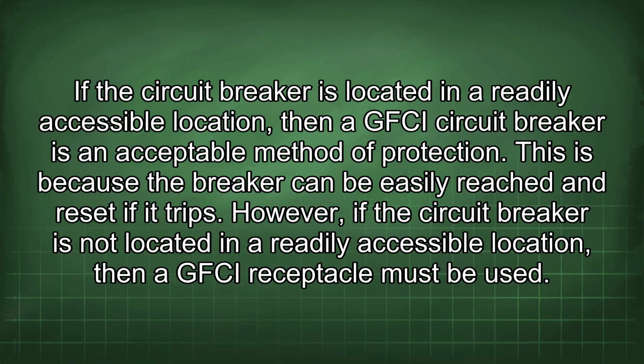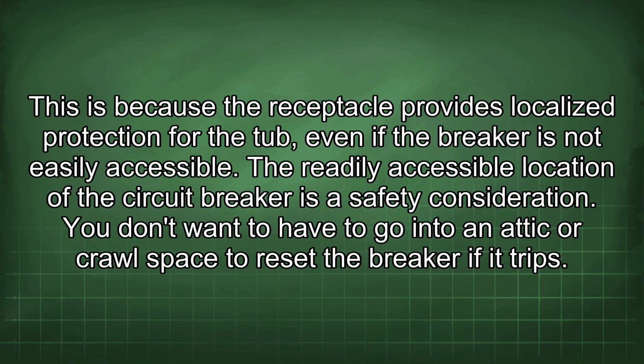However, if the circuit breaker is not located in a readily accessible location, then a GFCI receptacle must be used. This is because the receptacle provides localized protection for the tub, even if the breaker is not easily accessible. The readily accessible location of the circuit breaker is a safety consideration. You don't want to have to go into an attic or crawl space to reset the breaker if it trips.